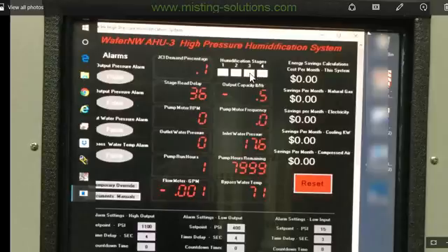Shut off stage 3, turn on stage 1, you've got 80%. Shut off stage 1, turn on stage 2, you've got 90%. Turn on all 4 zones and you've got 100% of capacity. And this JCI demand input would match these stage lights that are on. As this rises from 10 to 100%, you would see these stages match the capacity or the demand that's shown on this display.